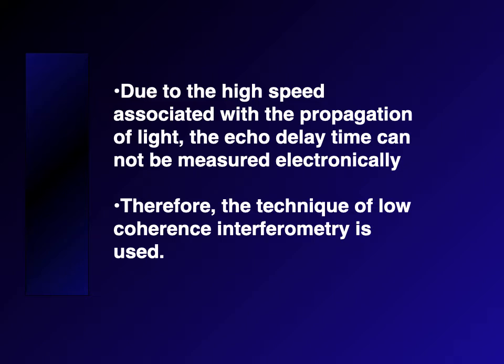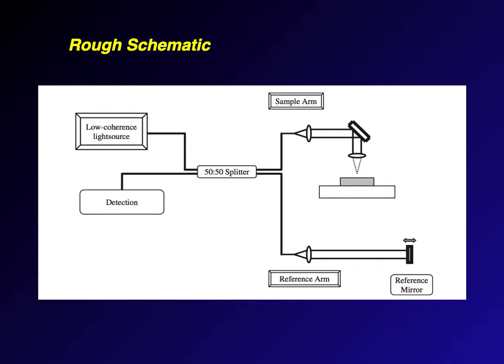Due to the high speed associated with the propagation of light, the echo delay time cannot be measured electronically. Therefore, the technique of low-coherence interferometry is used — that is actually the real name for OCT. In low-coherence interferometry, because you can't measure the time something goes and comes back like with ultrasound — light moves too fast — you use a reference arm. The physics of this is discussed in the lecture on axial resolution.